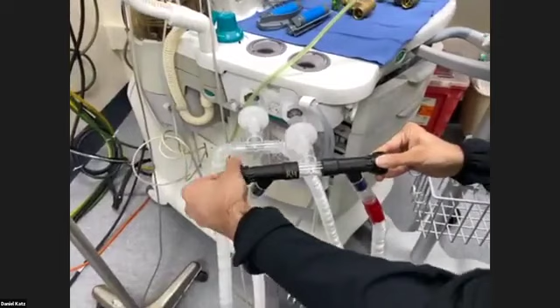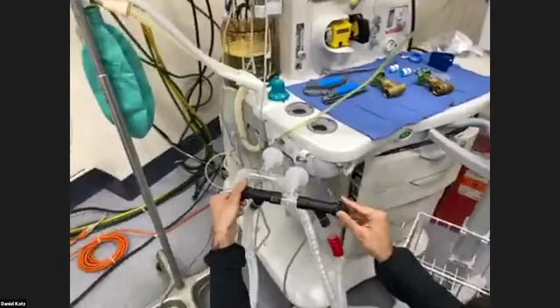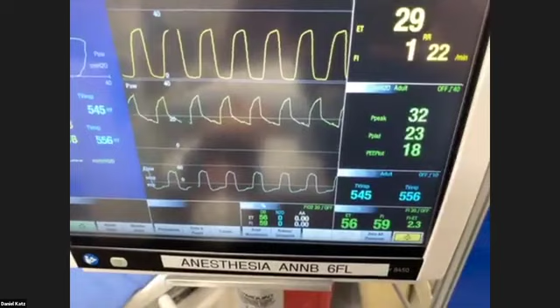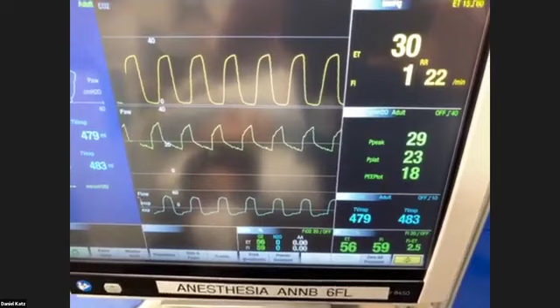Now, as I start to close this valve, you will see a change in your tidal volumes on this screen, and you will see that patient B's volumes do not really change at all. Just give me a quick second. I do want to go slow to show that it is very fine control. You can see that the volumes are starting to come down from 550 down to about 500 right now. You can see your peak pressures, plateau pressures, and your PEEP as well. And keep an eye on those variables as well.